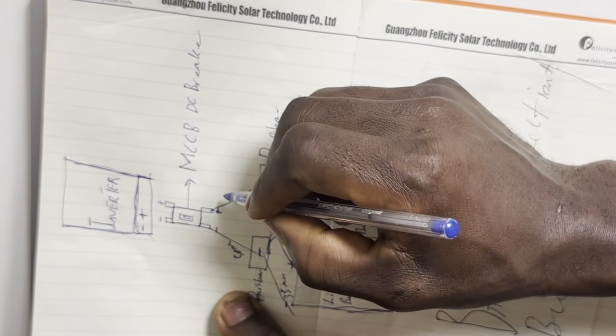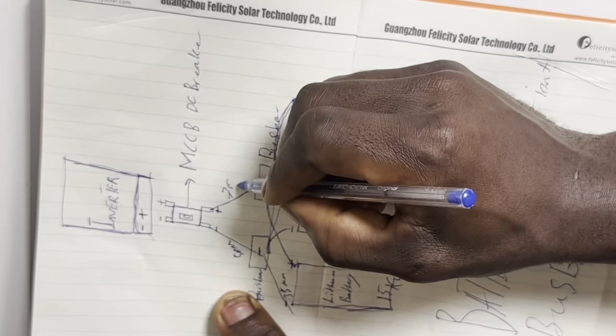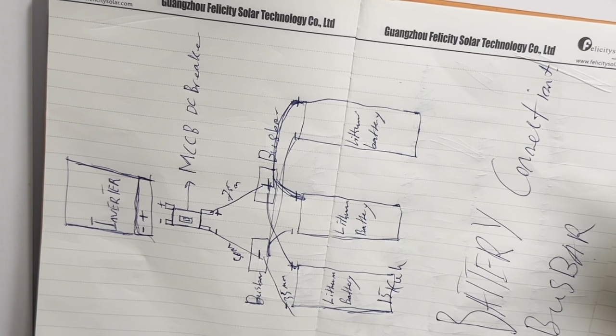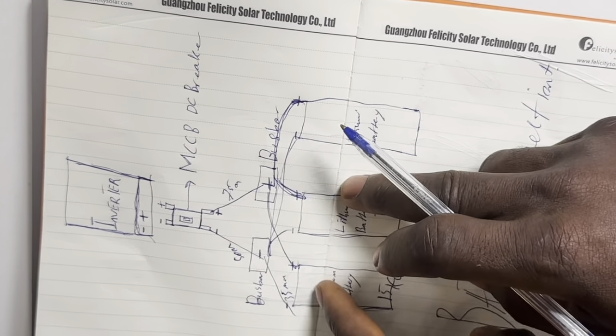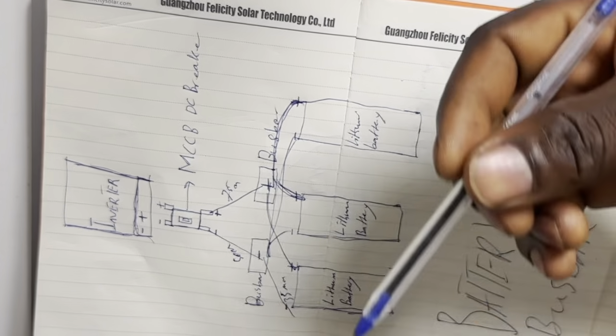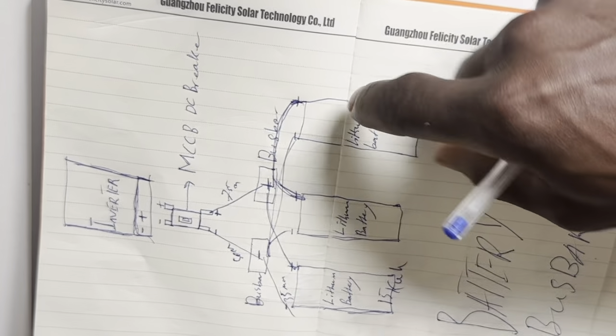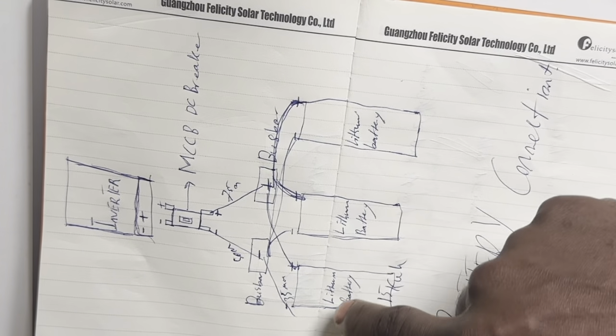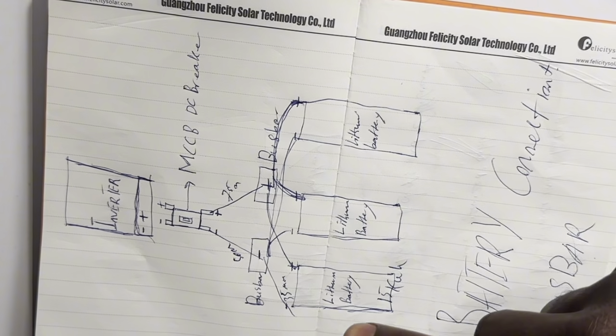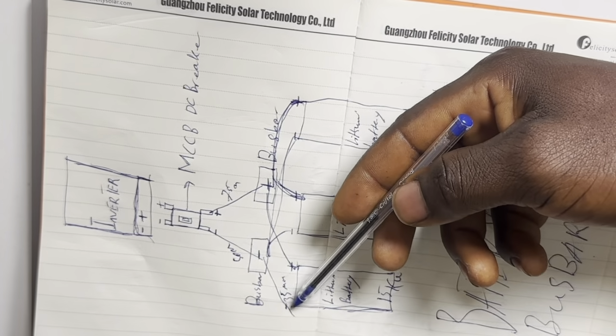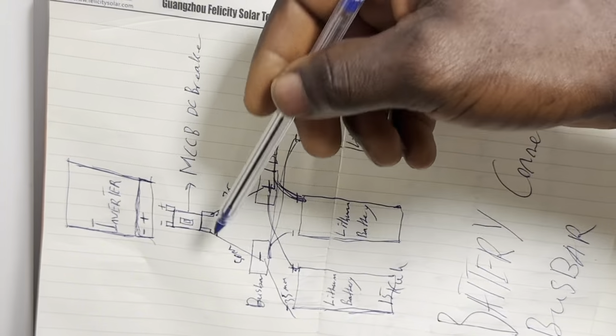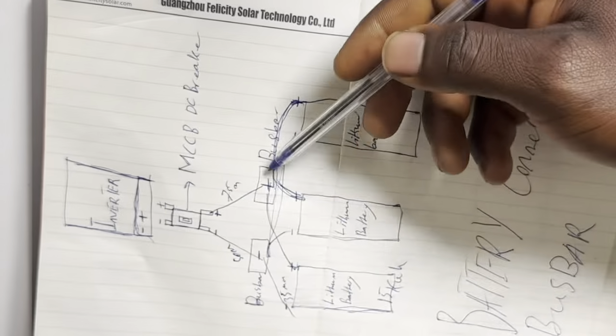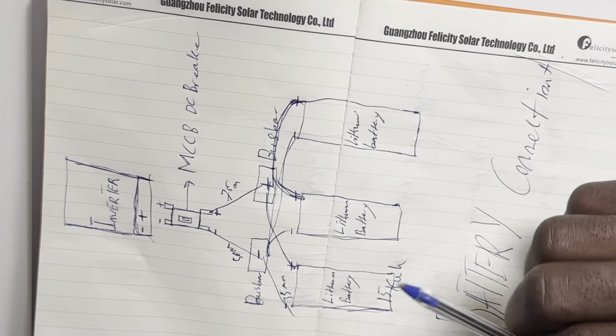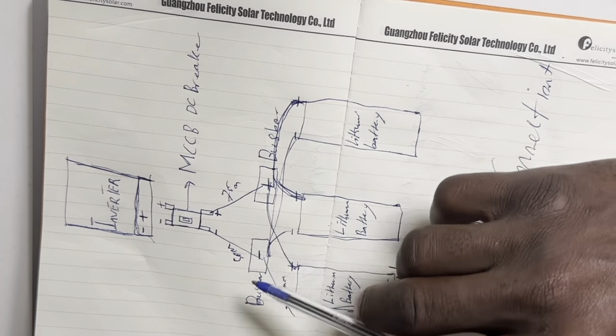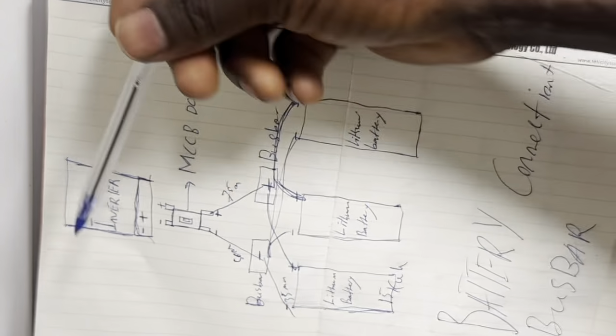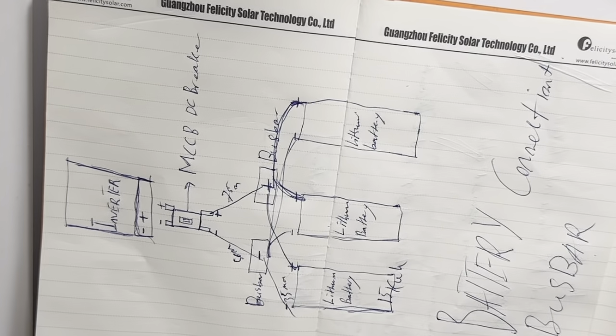Or even 75mm. That's one thing a lot of installers get wrong when connecting their bus bar, because you need to understand these lithium-ion batteries are different units, not just one battery. Once they're combined through this cable setup, if you're drawing energy from this bus bar - if each battery supplies 200 amps, that's 600 amps total going out to the inverter. That is the first thing you need to understand.